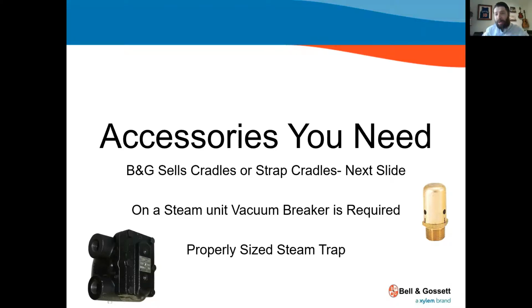What is a vacuum breaker? Well, if you have any water in the shell on the steam side, which you will, because as it condenses, it'll be on the bottom there, it creates a vacuum effect if anything flashes in the steam within that shell, and that can be destructive. That can create a lot of damage. So this little breaker basically just vents to the atmosphere, so a vacuum effect cannot be created. It breaks the vacuum, hence vacuum breaker. You must have this in a steam application. Must. Absolutely cannot go without.